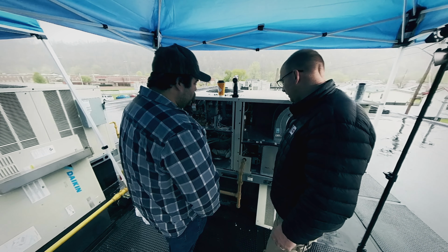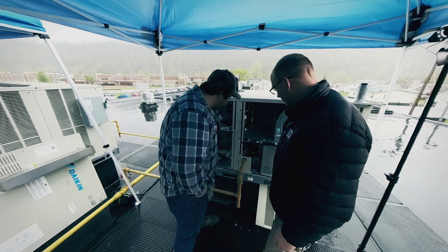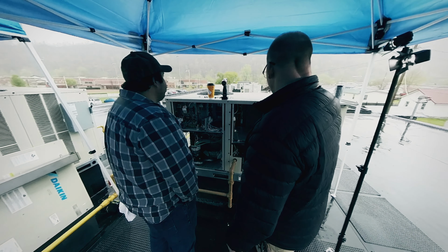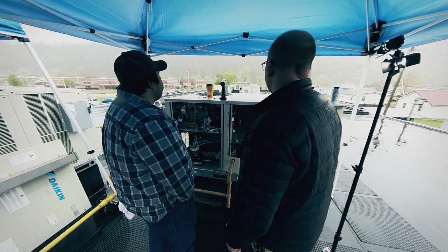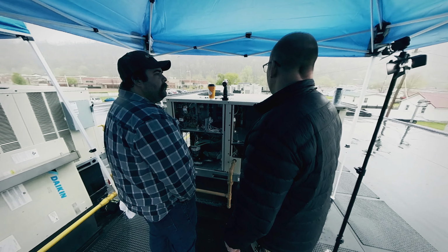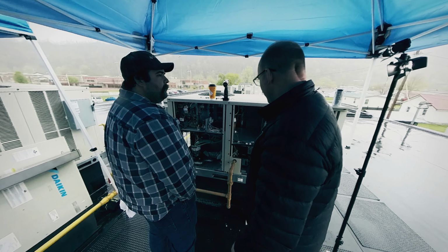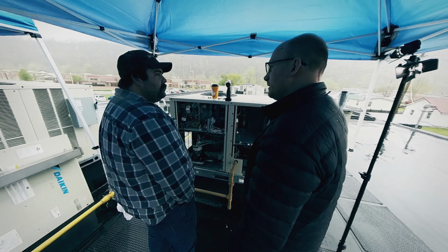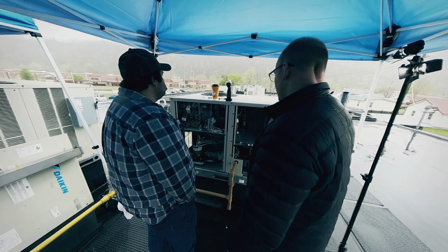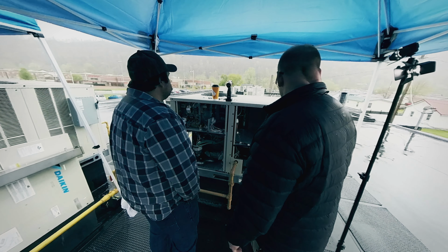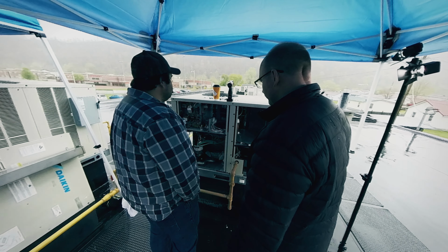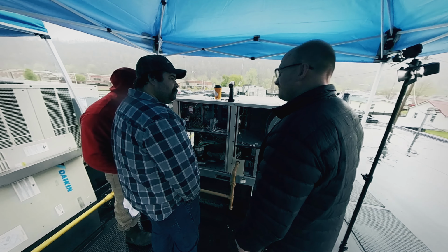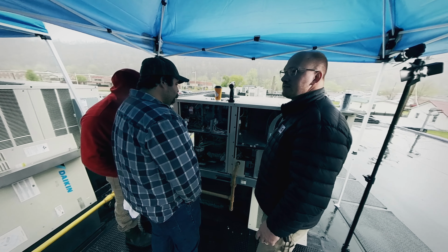They're not too bad. That unit right there, we had to replace the heat exchanger. That gas valve went bad and it was building up carbon inside, so even though it was brand new, we just went ahead and replaced it. Working a lot. Any questions?